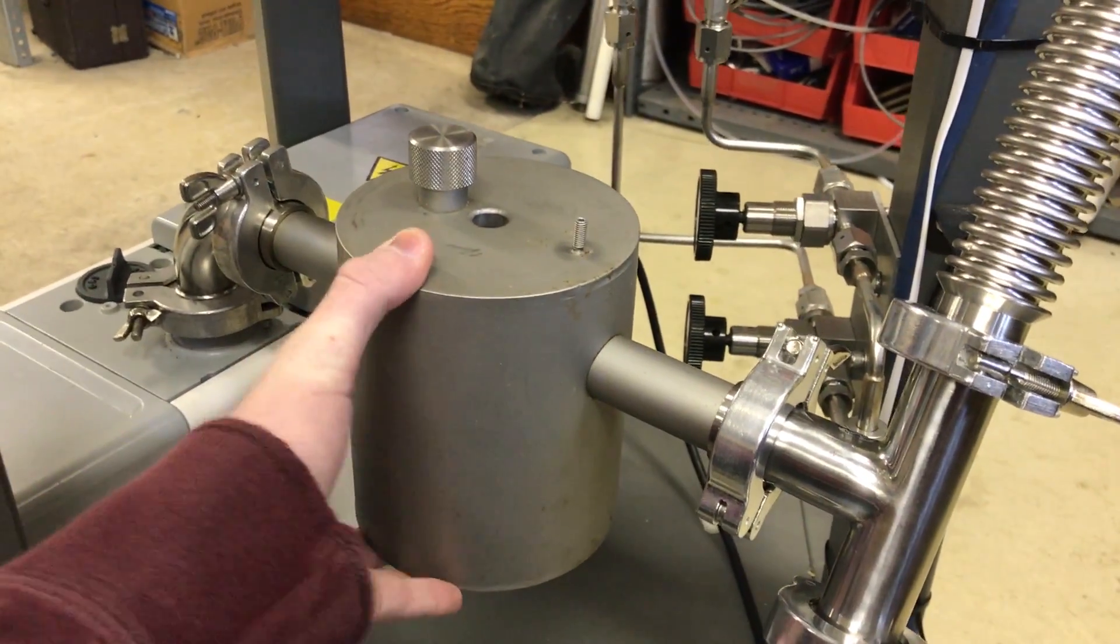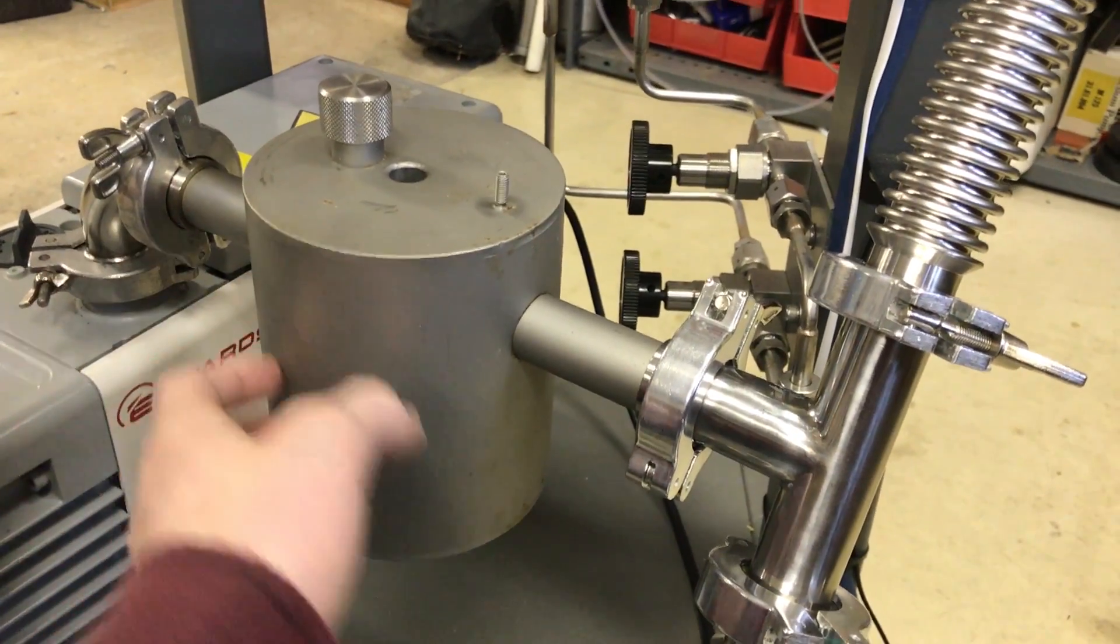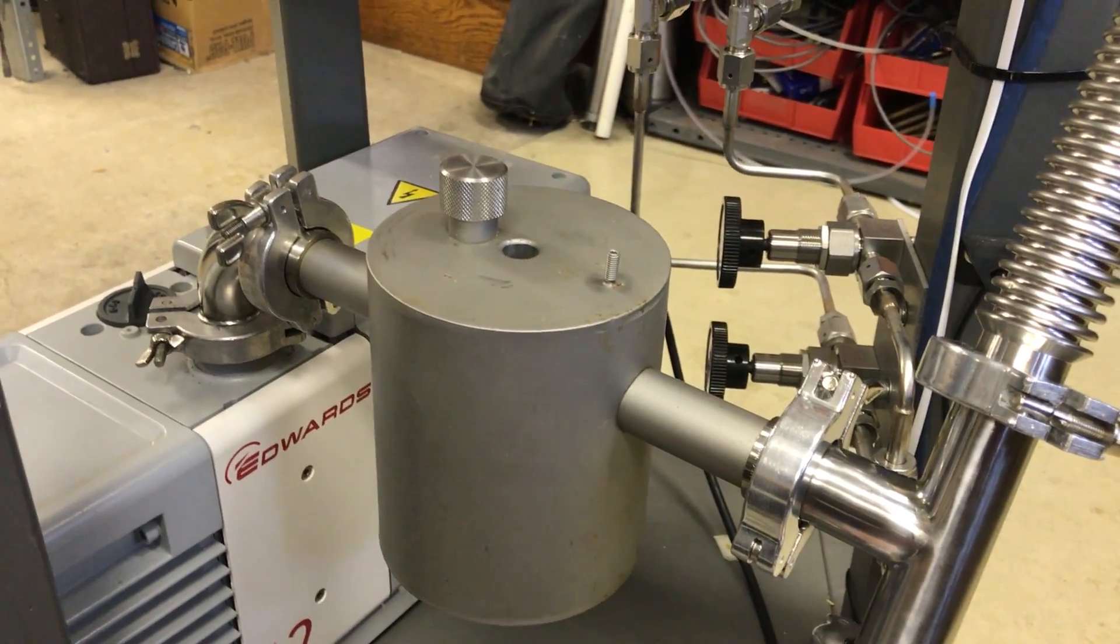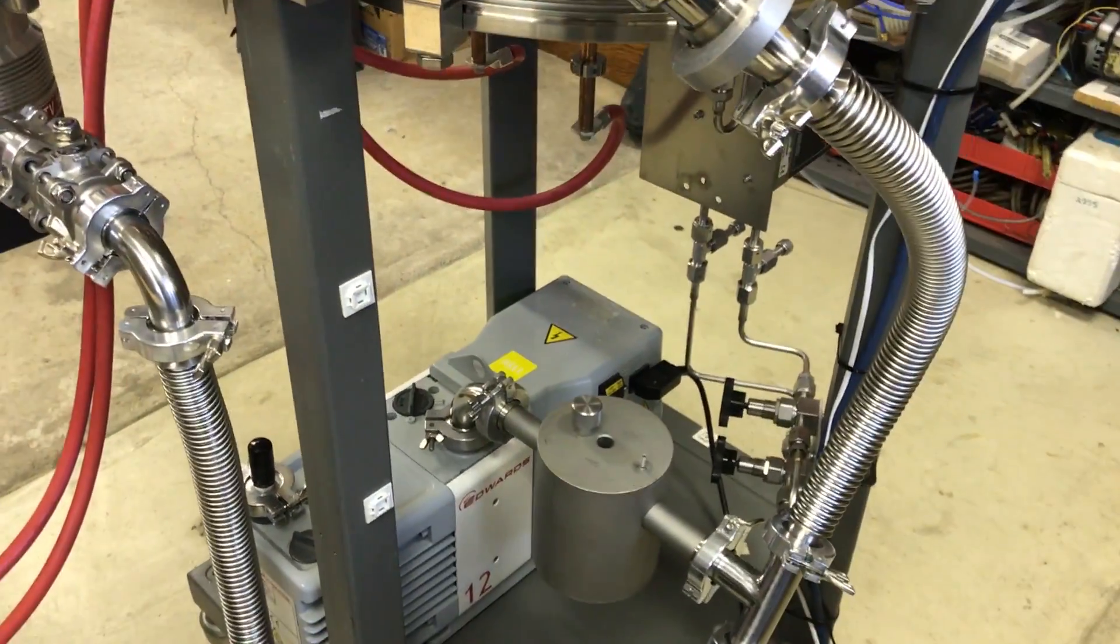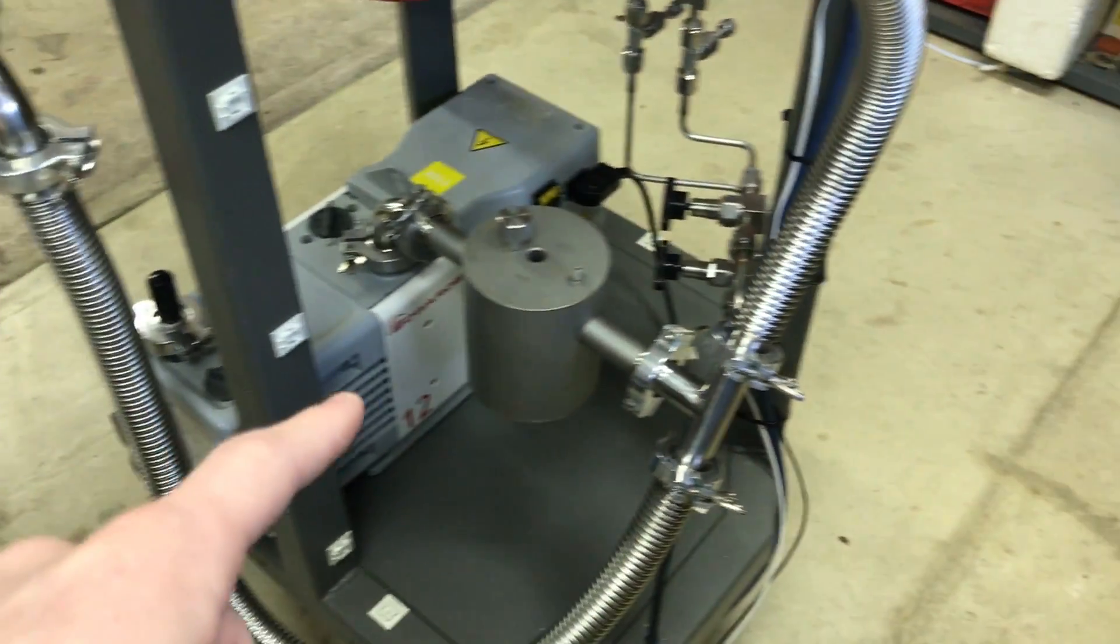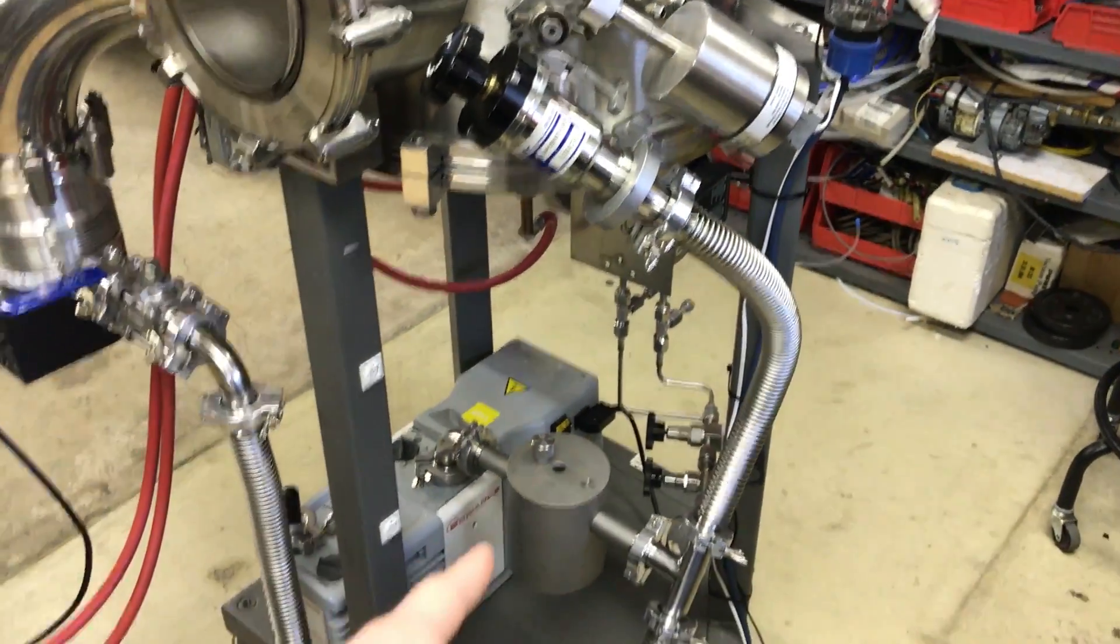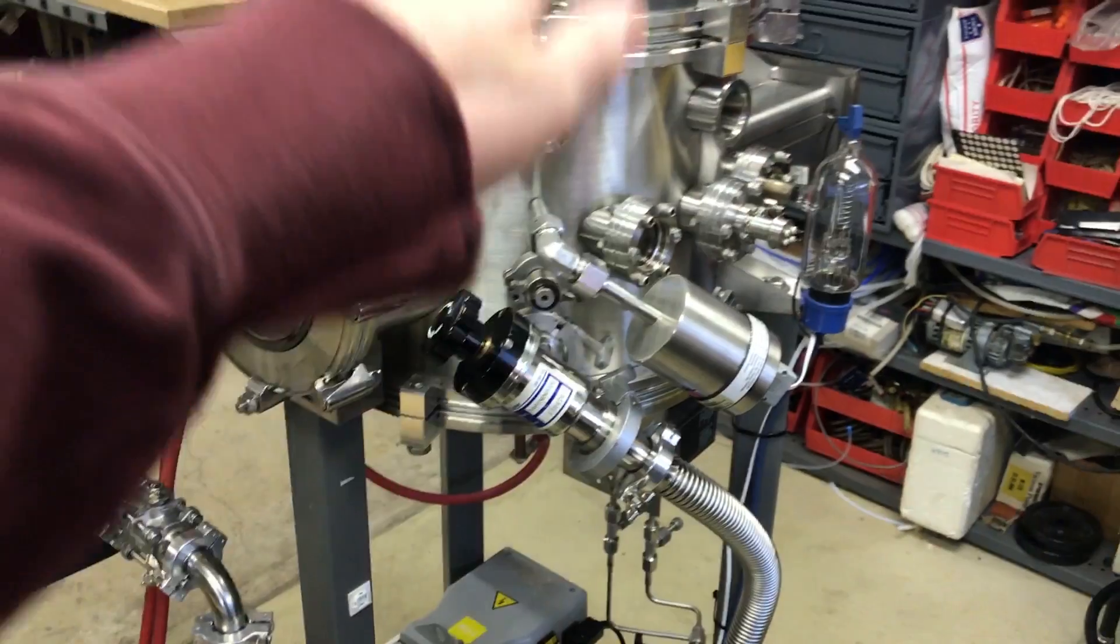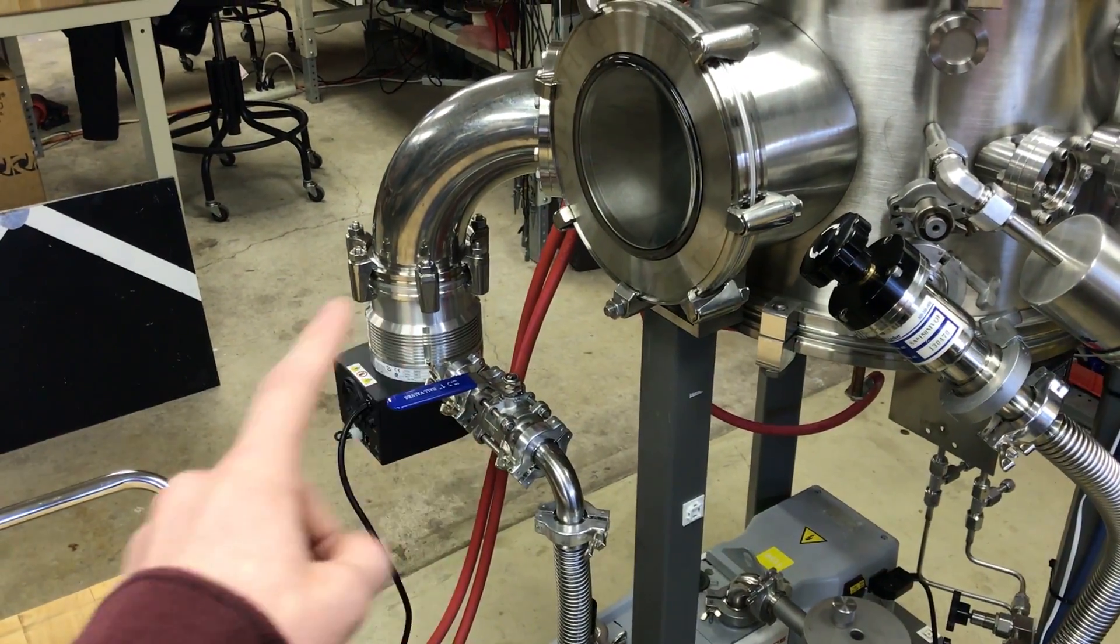This is a foreline trap, and there's a heater, a Watlow heater that goes in there. And it's got desiccant beads in it. And it slows things down a little bit when you're pumping, but it'll help the backstreaming of fluids into your chamber. So I have all the valves set up so that when I want to pump down the chamber initially, I close that valve and open that valve there so that I'm pumping down from the mechanical pump straight to the chamber.